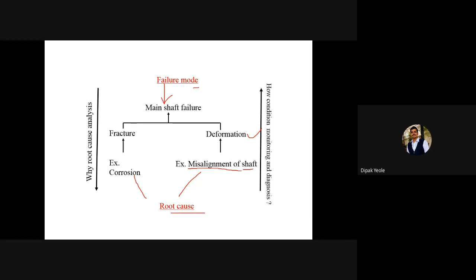Now what are the failure modes or root causes? You can say the types. The defective design of the manufacturer can lead to failure; that is a root cause. The second is defective material. The third is defective installation, overspeed, overload, component failure, excessive temperature, winding over temperature, and bearing over temperature.